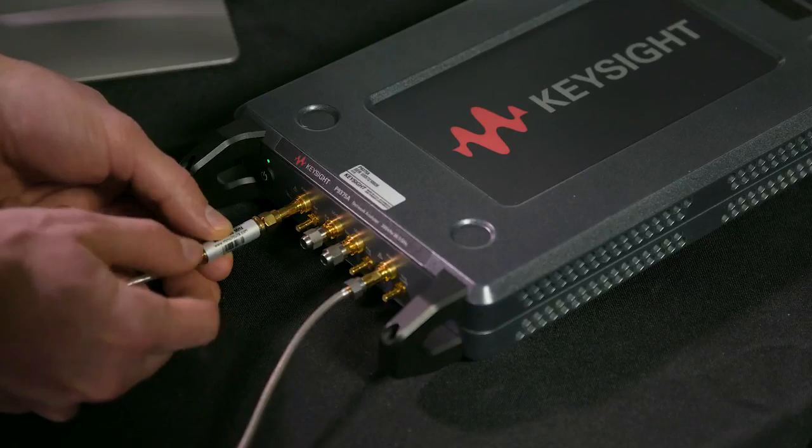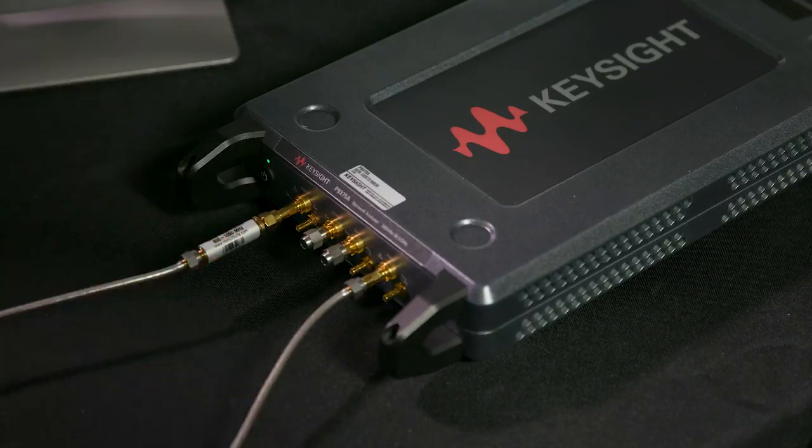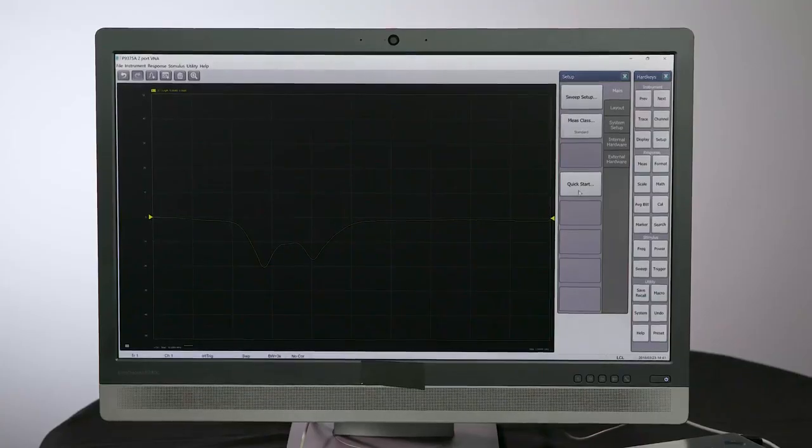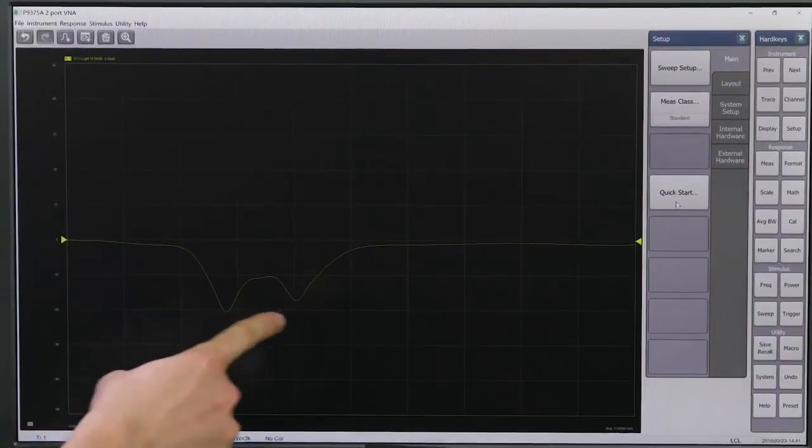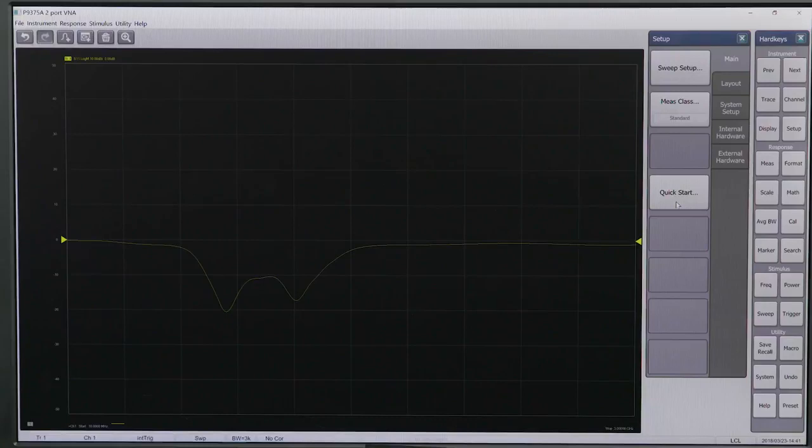Now, let's connect the DUT to port 1 and the test cable coming from port 2 and ensure we can see the signal on screen. We can see the measured S11 parameter in magnitude on the screen as the default parameter, just as we set in the quick setup.